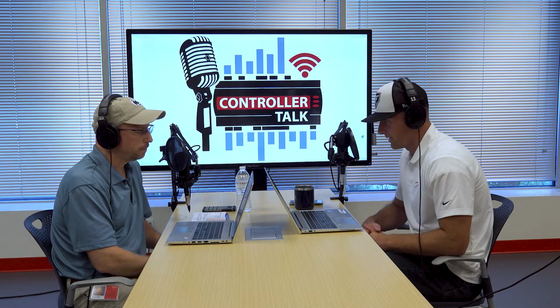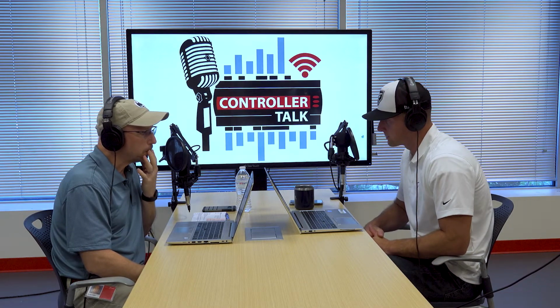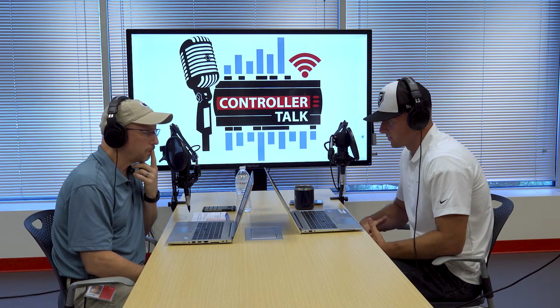Yep. Emailing alarms is something else that we get into now. You get some people that maybe aren't using a monitoring service, but they still want some notification of when something happens in their store or with their controller. So the SM-800 uses that older SMTP format with no encryption to it. We've talked some about SSL and some of the other encryptions that the new 800A has, but that's not anything that the 800 supports. So it's just your generic SMTP format there.